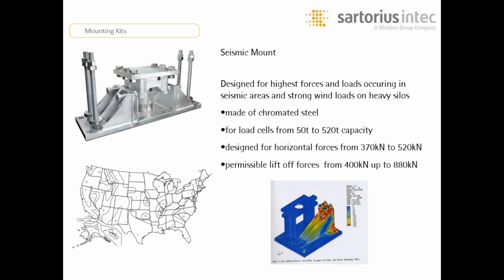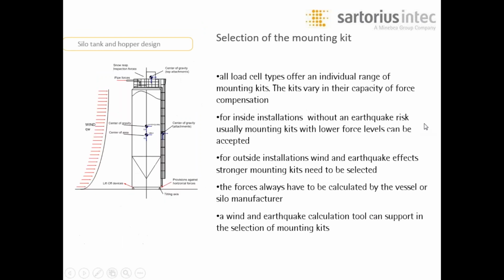The seismic mount is designed to be used in areas that are known to have a high propensity of seismic activity. As you can see, there are many areas of the U.S. that require special considerations when designing a tank or silo system. All load cell types offer an individual range of mounting kits. The kits vary in their capacity of force and compensation.